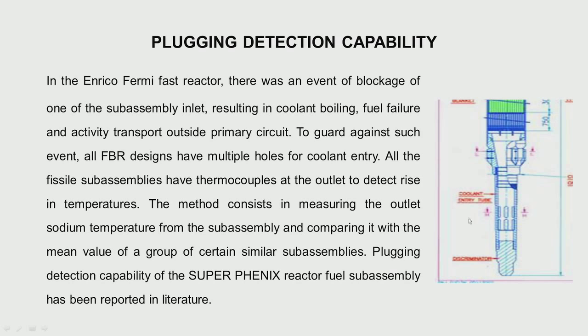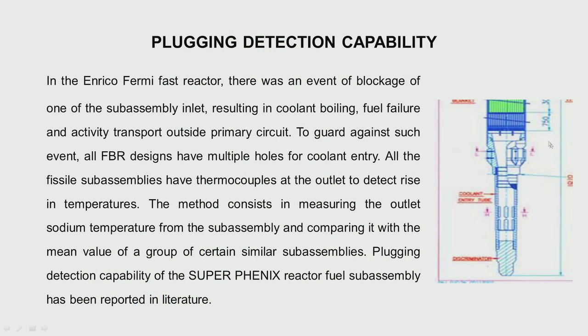After that reactor incident, one thing was sure — we can't say that any hole will not be blocked or plugged. So in all reactors subsequent to the Enrico Fermi reactor, the whole world's reactors, the subassembly gets coolant not only from the bottom hole but also from side holes. There are multiple holes for entry of the coolant, and at the outlet of every fuel subassembly, we have thermocouples which monitor the temperature. In case there is a temperature increase, they would be able to detect it and forewarn us that that assembly is not getting enough flow.